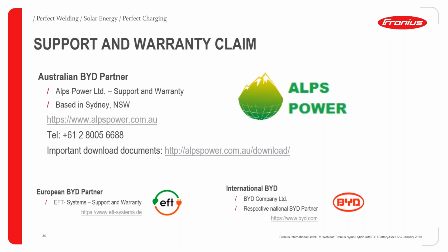One of the things when you're doing commissioning, which I did forget to put into the webinar, is when you're turning it on after commissioning, you want to turn the battery on first and then turn the inverter on. The reason is the BYD has a special safety mechanism that looks for or detects any DC on its input. When the inverter is switched on, there's always a bit of leakage voltage between the inputs. So if you've got your PV there, you get a bit of leakage voltage through to the battery input, and if the battery sees that, it won't start up—it'll shut itself down. So if you're having issues, turn the battery on first, leave it for 10 or 30 seconds, that's enough, and then turn the inverter on and power it up that way.